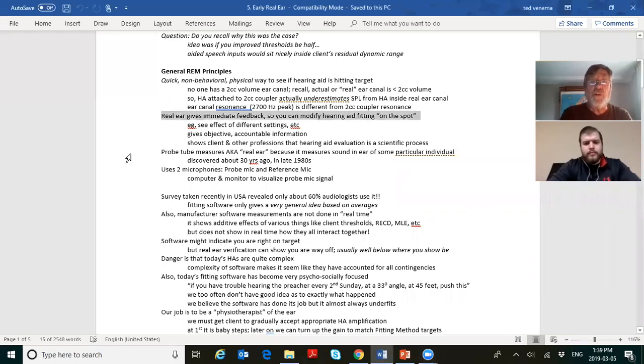Probe tube measures, also known as real ear, because you are measuring the sound in the ear of some particular individual. Real ear has been around for about 30 years. But the old real ear has been used for years and years. The new real ear, called speech mapping, has only been used mainly in the last 10 years. Before that, it was REUR, REAR, and real ear insertion gain.